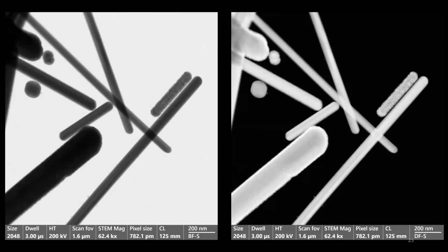And this is STEM. The cool thing about STEM is you can take both dark field and bright field at the same time. We can change the camera length of the machine so that we can even, because we have 3 detectors, it's 3 rings. One's a circle in the center, and then we have 2 rings around that. We can extend bright field clear out to all of those. So all 3 of the detectors are doing bright field, or we can take it all the way so that we're doing high angle dark field.